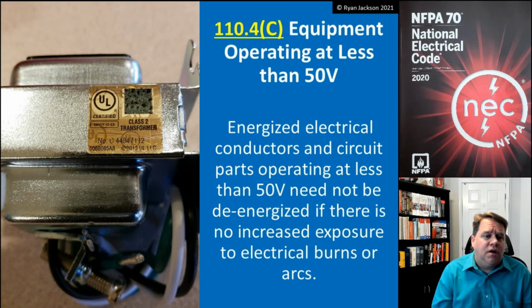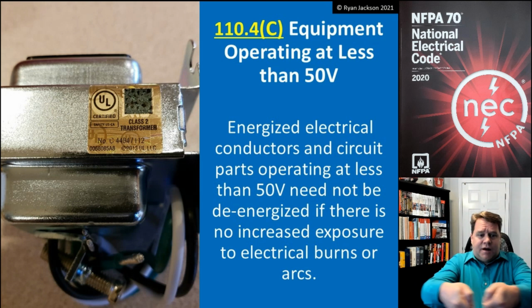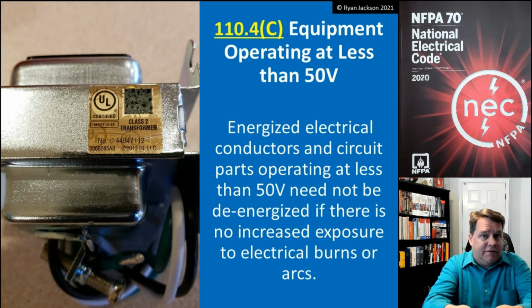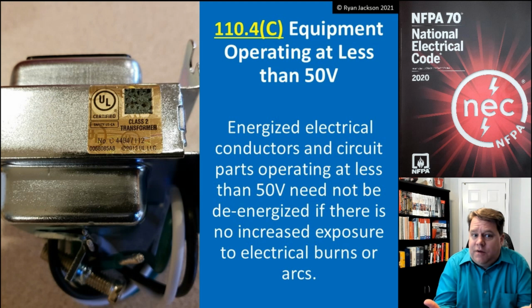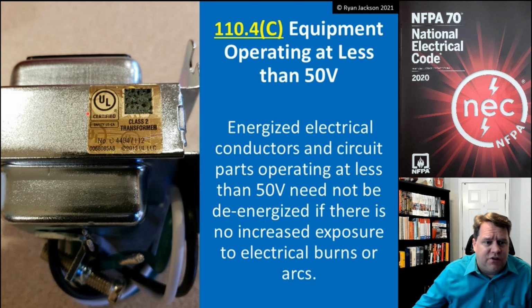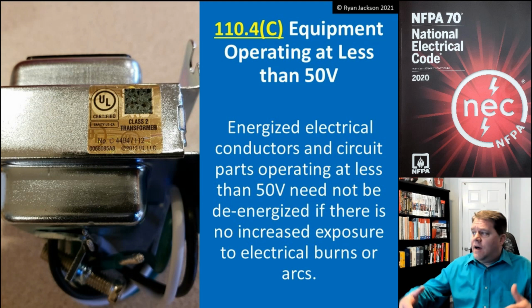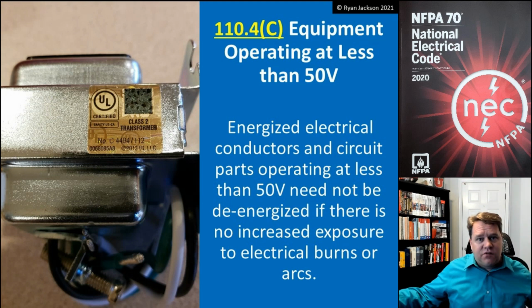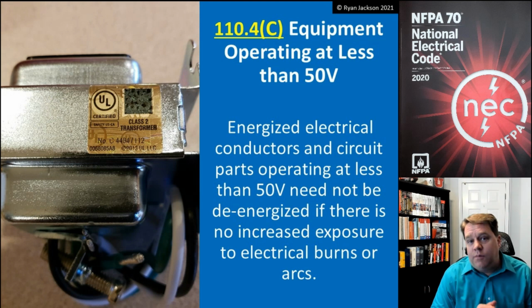But when it comes to an arc flash, that's dependent on other variables. I'm showing a class 2 transformer, a doorbell transformer. You take the black and white wire off the secondary of that, and you're not going to be able to cause an arc flash with this thing. There's just not enough power involved. Does that mean that anything less than 50 volts is safe? Well, no, not necessarily. I could have a bank of batteries that takes up an entire room of a building. It might only be 48 volts, but it might have a ton of available fault current.